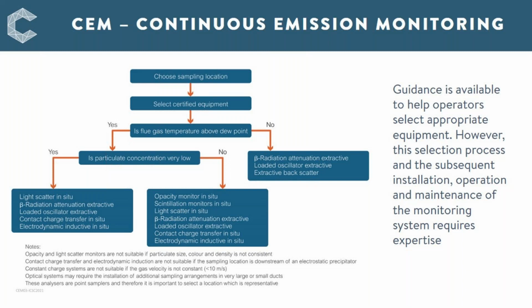So it has to be somewhere where staff can reach this access by stairs on the outside of a chimney and install a fairly sensitive measurement unit which must be safe from the outside interferences, such as weather. At the same time, the position inside the stack must ensure a representative sample, and so it must be away from any equipment in the stack which may affect the flow and the homogeneity of the stack gas mix. Testing is therefore required before the final sampling location is decided.